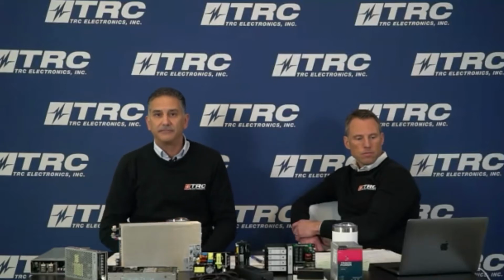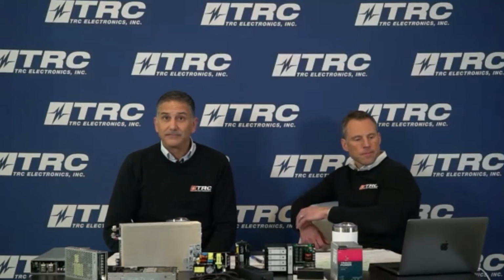Yeah, so that product has been great for what you said. One of the big applications, like you mentioned, is lighting. It can be used a lot in large scale buildings, warehouses, factories and such. They run 480 three-phase into the building, and when you split those phases off single phase, you get the nominal 277.